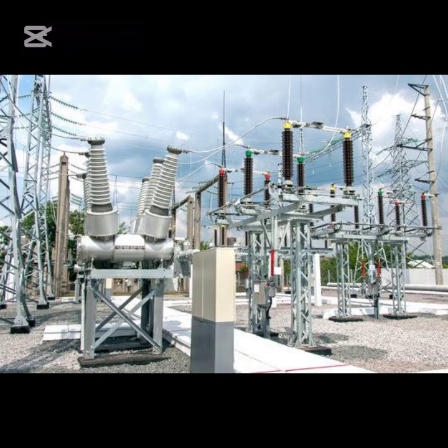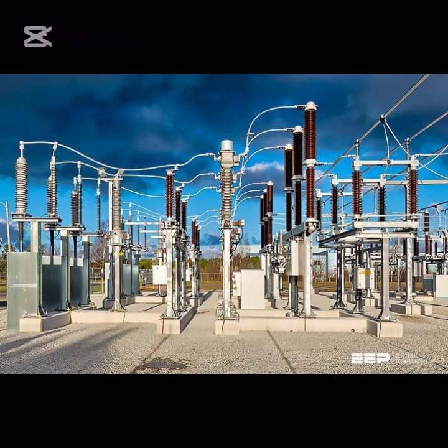Based on the voltage level involved, switchgear is generally divided into two categories: indoor and outdoor types. For outdoor type, when the voltage exceeds 66 kV, switchgear is usually installed outdoors. This is because at such high voltages, the required spacing between conductors and the physical space needed for equipment like switches, circuit breakers, and transformers becomes so large that indoor installation is not safe.